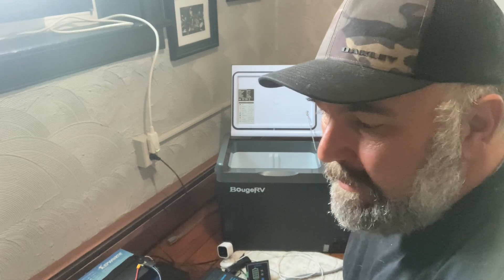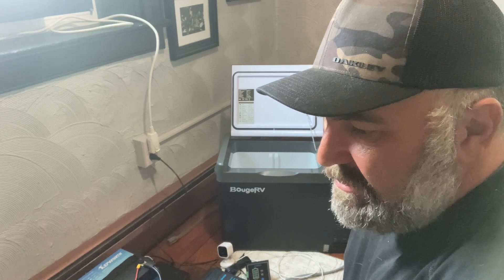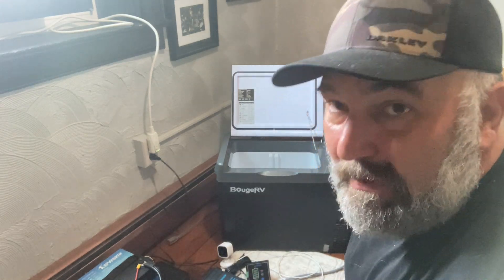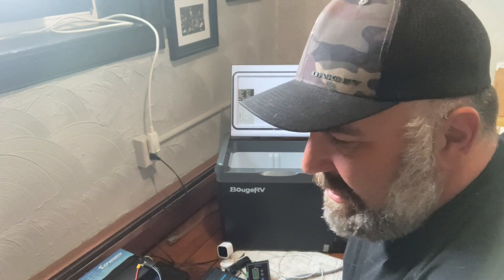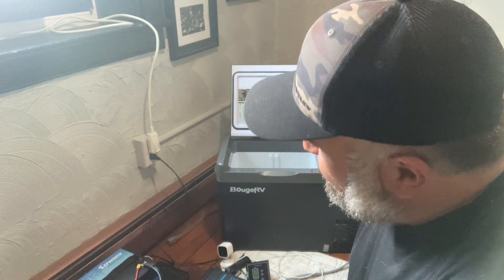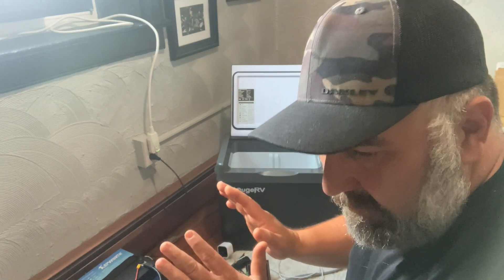When the battery is completely depleted, a 7 amp charger will take around 14 to 15 hours to fully charge it. That's a long time — especially if you're on an off-grid setup running a gas generator to charge things. 15 hours on a generator would really be a problem, so the charging rate is something to think about.